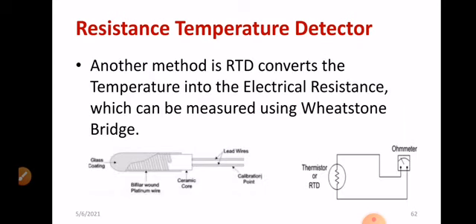Moving on to the further discussion. Another method is that the R.T.D converts the temperature into electrical resistance, which can be measured by using a Wheatstone bridge. You can apply the balancing principle of the Wheatstone bridge, which I will show you in the next slide. So this is the schematic diagram of an R.T.D. We can see the glass coating, then the lead wire is available. The lead wire is mainly used for calibration, that means for extending the range. And we have the ceramic core here, and inside you can see the platinum wire at the bottom side, exactly inside. That platinum wire resistance will be measured with respect to the change in temperature. The resistance of the platinum wire varies. That resistance will be measured with the help of a Wheatstone bridge. That I will be showing in the next slide.